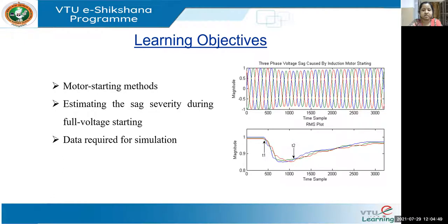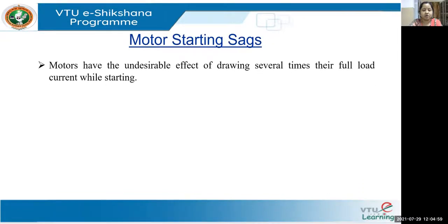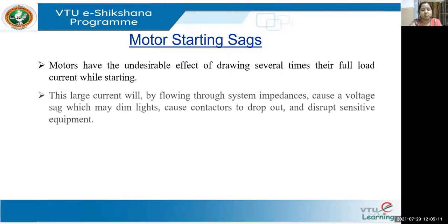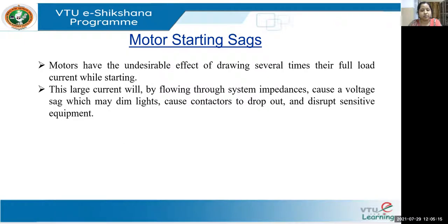We have usually seen a dip in voltage whenever any motor starts. In motor starting, there is an undesirable effect — the drawing of several times of full load current when it starts. This large current, flowing through the system impedances, will cause a dip in voltage, which is sometimes visible to our eyes when light intensity reduces. We notice that in day-to-day life, which gives us an idea that there is a dip in voltage.